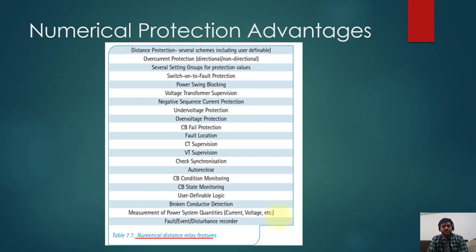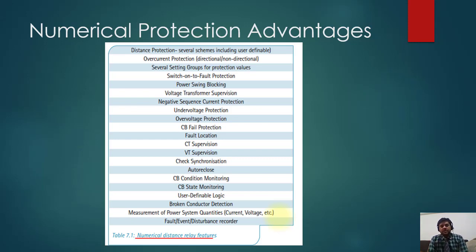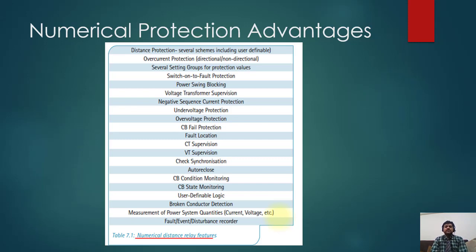Numerical protection provides many advantages: distance protection with several schemes including user-definable schemes, over-current protection that can be directional or non-directional, several setting groups, switch-on-to-fault protection, power swing blocking, voltage transformer supervision, negative sequence current protection, under/over voltage protection, CB failure protection, fault location, CT/VT supervision, check synchronism, auto-reclosing, CB condition monitoring, state monitoring, user-defined logic, broken conductor detection, measurement of power system quantities such as current and voltage, and fault event disturbance recording.